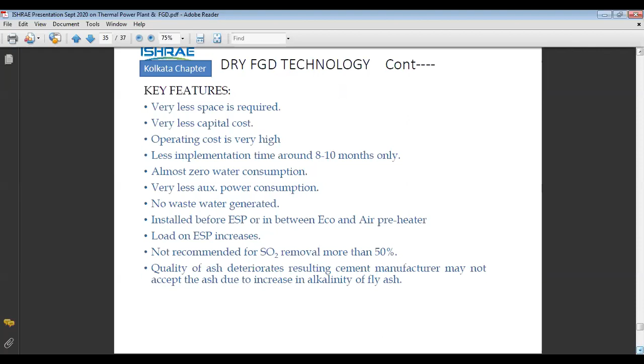One more thing is that the quality of ash deteriorates, so the cement manufacturer may not accept the ash due to the increasing alkalinity of fly ash. Because we are injecting this reagent before the ESP, the characteristic of the ash will change. What the new characteristic will be can be checked after installation, whether it meets the requirement of the cement manufacturer or not. If it does not meet it, then the entire ash we are selling may not be acceptable to them, and we will have to dispose of it. So this is the disadvantage of this technology.